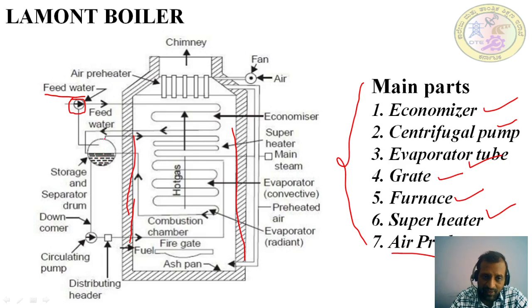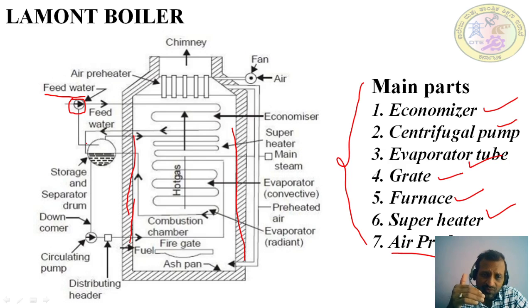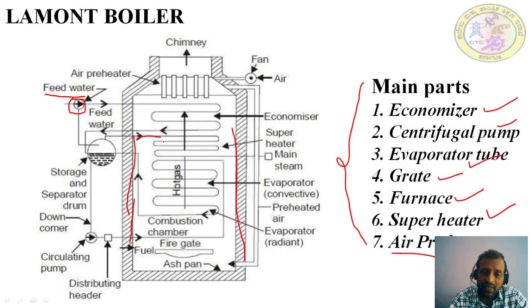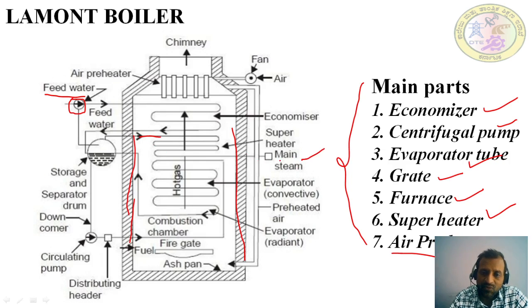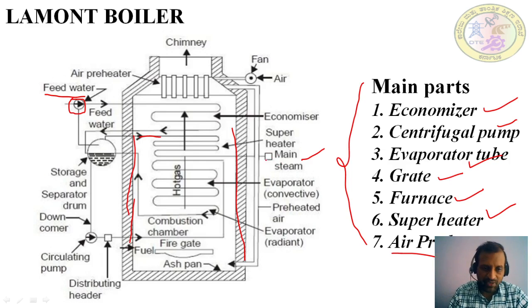From the storage and separating drum, the next component is the superheater. When water enters the storage and separating drum, half of the water gets converted into steam. That steam is sent through the superheater, which is also located in the path of the flue gases. Heat exchange takes place again, and that steam gets converted into superheated steam. This superheated steam connects directly to the main steam line, from which it is extracted for further applications.